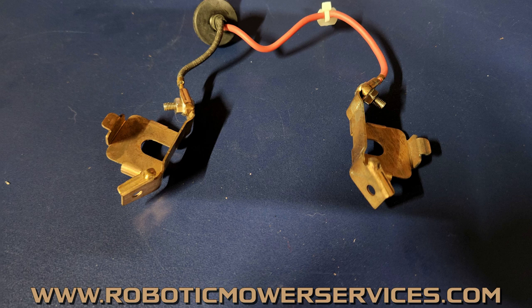And again, these have those plates where the wires are connected to those plates with a screw. Sometimes the nut will come loose on that screw, the wire will be a little bit loose and not making good contact. Check all that stuff out. Take those screws out, clean those plates up, clean the end of the wires up. Make sure that you've got good continuity there between the wires, the plates, hardware, and all that stuff.